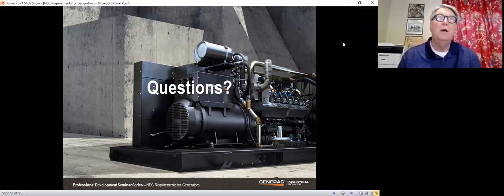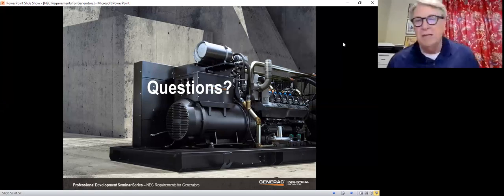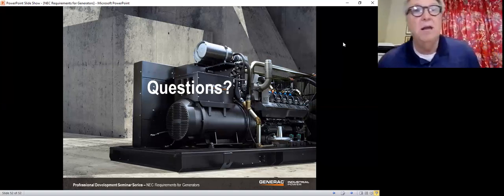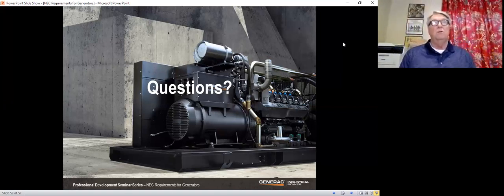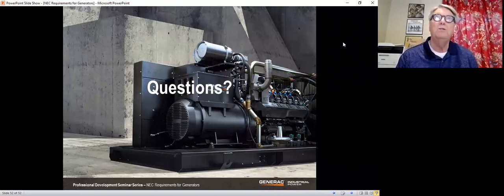Nope. The code basically, there is the section that we talked about on how big a generator needs to be, and basically they're saying it either needs to be Article 220, which is your typical how you size a service entrance, or other approved method. And basically, we just size generators to be big enough to run the load. Now, it can't be really smaller than what's necessary to run the load, nor would you want it to be that, but it can be bigger. And in theory, you could use a 2 megawatt generator on a 1 kilowatt load, and that would not violate the code in any way.